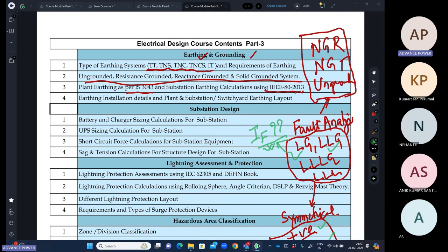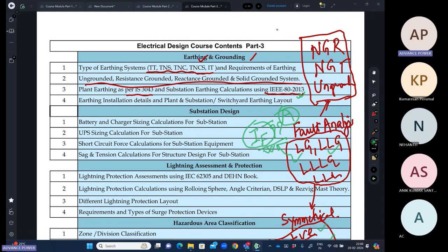For designing an earthing or grounding system, the first thing required is the earth fault current, from which we calculate the area of conductor required. After the area of conductor, we calculate the effective resistance of the grid. After that, we calculate the ground potential rise that will happen when the fault occurs. Further, this ground potential rise will be compared with the tolerable step and touch potential of a human body.